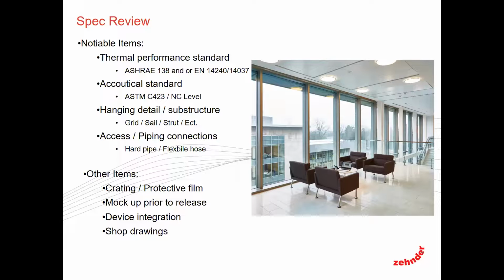And then the other thing I want to mention, depending on the project size, is mock-ups. Mock-ups prior to release are extremely important, especially for larger project sizes, when we're talking 20, 30, 40, 50,000 square feet of panel, to make sure that the integration is being done properly, the cutouts are being done properly, and Division 9 is on the same page as Division 23. Then that gives the entire design team a chance to sign off on everything, and everyone's happy with what they're getting.